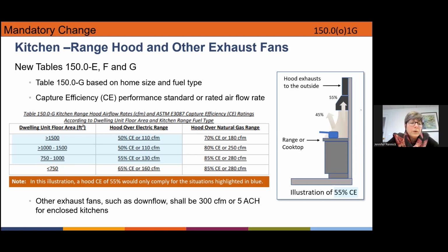In these new tables, the CEC, with support from research done by the EPA and other entities, recognized that emissions coming off a natural gas range are higher, with more pollution than coming off an electric range. So the gas range needs higher capture efficiency or higher CFM in order to be effective and have good air quality in the unit.